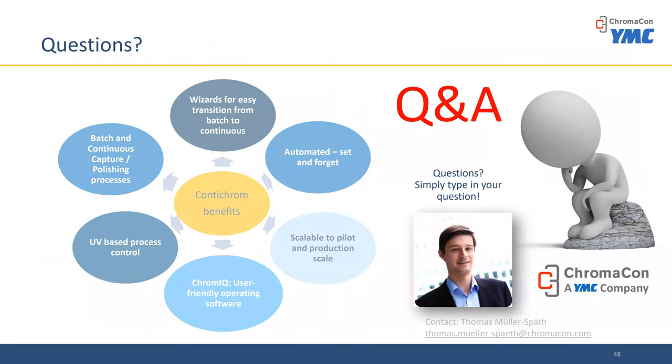Thank you for your questions. First question: Thomas, are these systems available in Korea? Yes, they are available in Korea. There is YMC Korea, our branch office, and they have a lab and support these systems. Next question: what special columns are required to run the two column processes? You can use any columns that you would also use in single column chromatography for this multi-column process. They tend to have shorter bed height, which will lead to an increase in productivity. It's also possible to use the system with membrane adsorbers — we've done that for both capture and polishing.